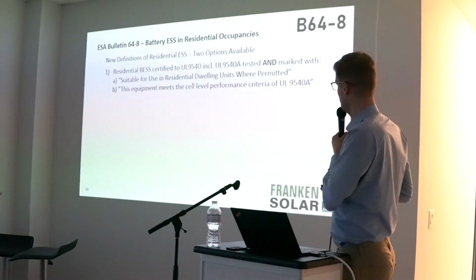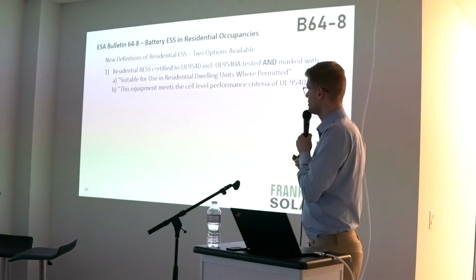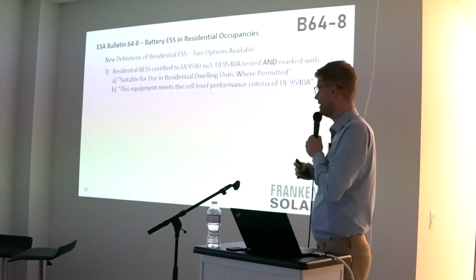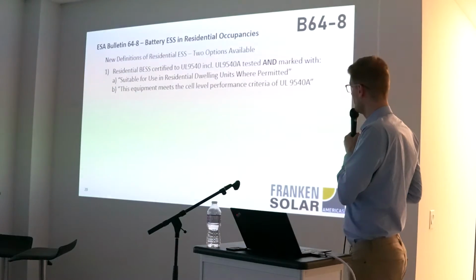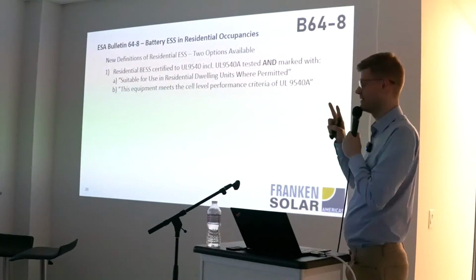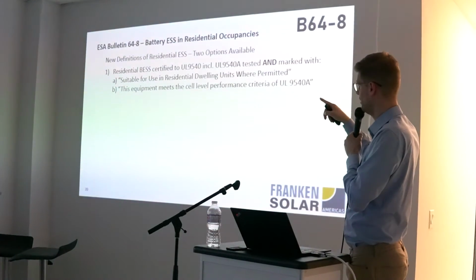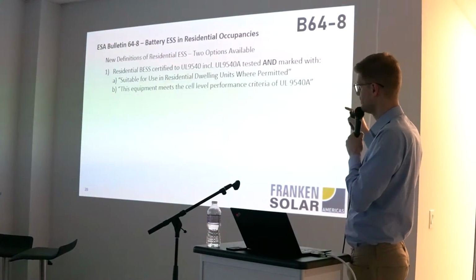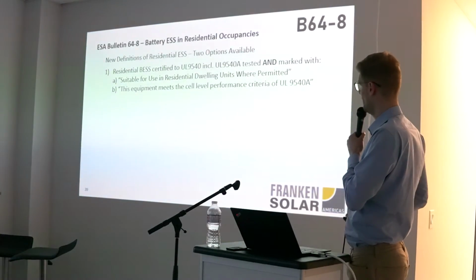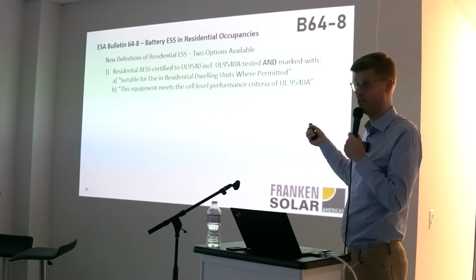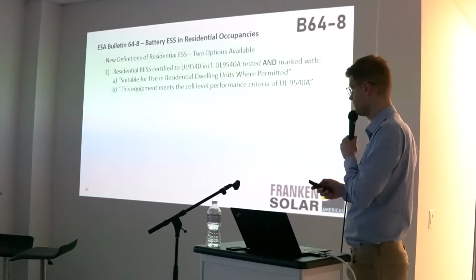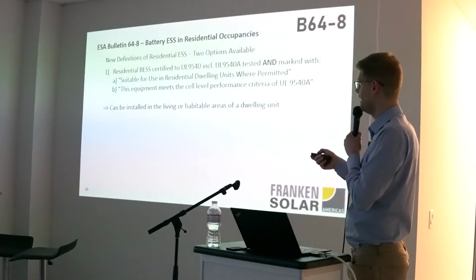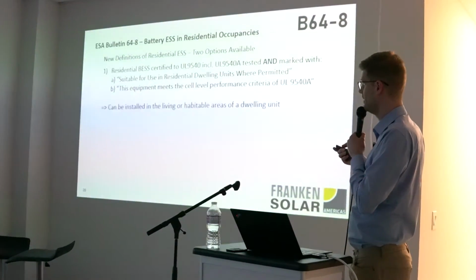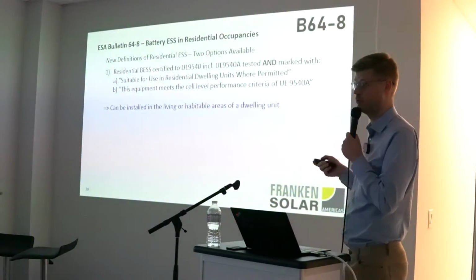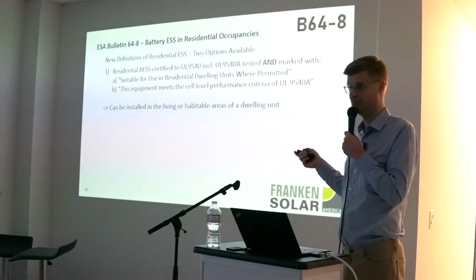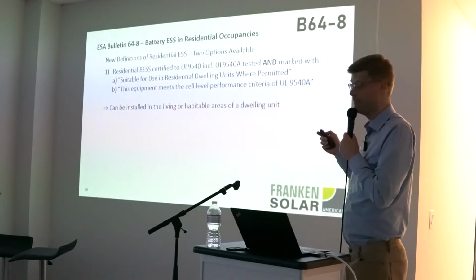So, first option, and that's probably the easiest: the residential battery storage system is certified to 9540 and the 9540A testing, and is marked with the two sentences we already have, suitable for use in residential dwelling units where permitted. This equipment meets the cell level performance criteria of UL9540A. We already know this is not going to happen. It's not the case right now. Second option, or here, if you have that, you can install that in the living or habitable areas of a dwelling. That would be your living room or even your bedroom. How about your basement? That can also be installed in the basement.